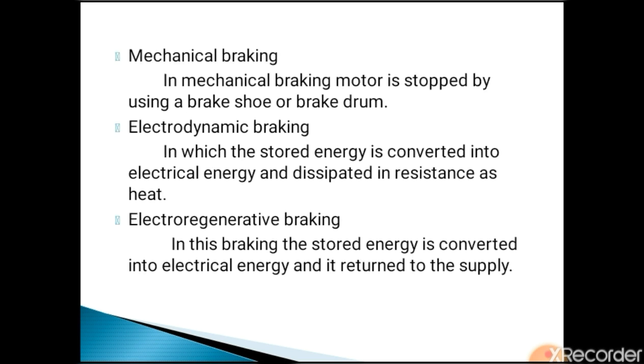Mechanical braking is provided to stop the motor quickly, which can be accomplished by the use of either mechanical brakes or electric brakes. In mechanical braking, the motor is stopped by using a brake shoe or brake drum. In electrodynamic braking, the stored energy is converted into electrical energy and dissipated in resistance as heat. In electro-regenerative braking, the stored energy is converted into electrical energy and returned to the supply, so the energy is not wasted.